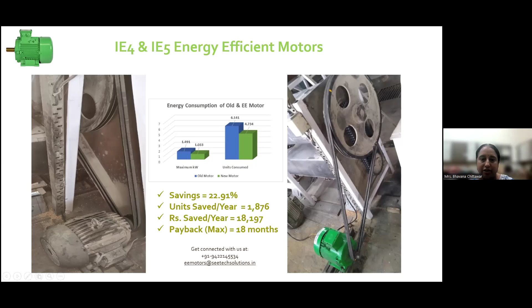The savings here are 22.91%, units saved per year is 1876, and rupees saved is 18197, with a payback period of 18 months. This is just one very small motor; in industries and buildings there are n numbers of motors. Wherever possible, some may have operational limitations where we should not touch them, but in most places this replacement can be done and savings obtained.